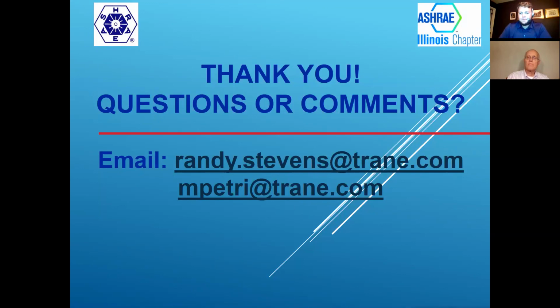Another couple questions here. The first one would be, can you provide some guidance for distances, both vertical and horizontal, between air handlers and condensing units to make sure oil return to compressors is not compromised? Yeah, so we have a piping guide that we can send you if you email one of us here. We cover Trane equipment, but like I said, you need to contact the manufacturer that you're dealing with. Our guidelines are strictly for Trane equipment.